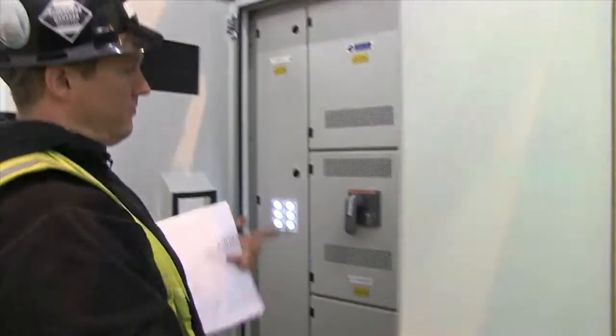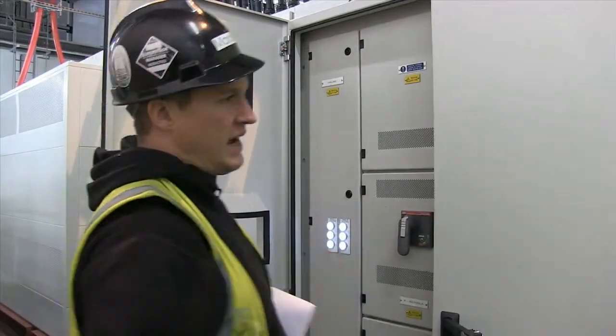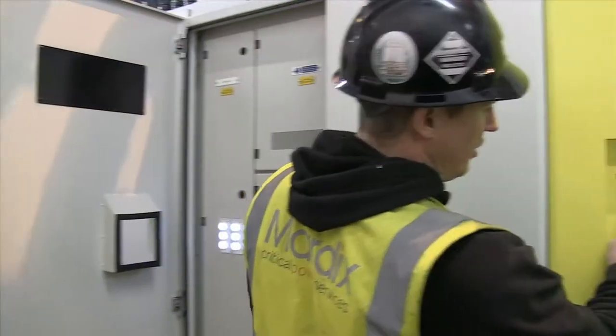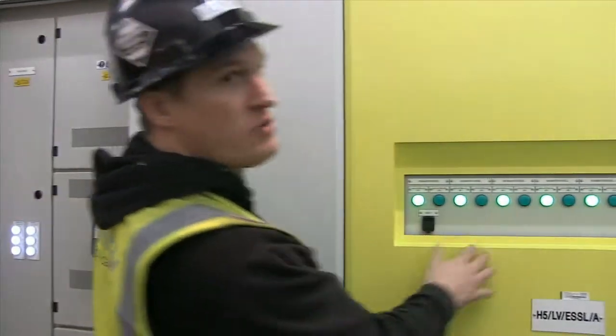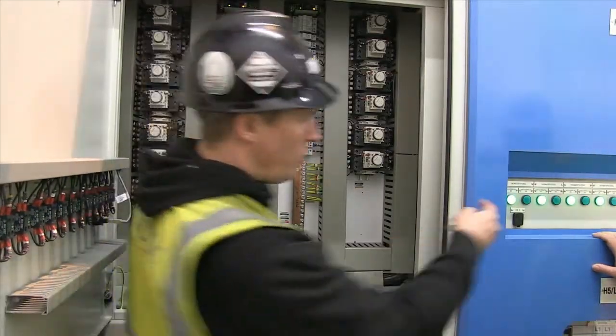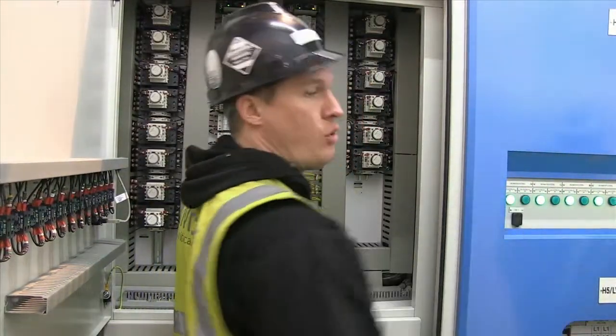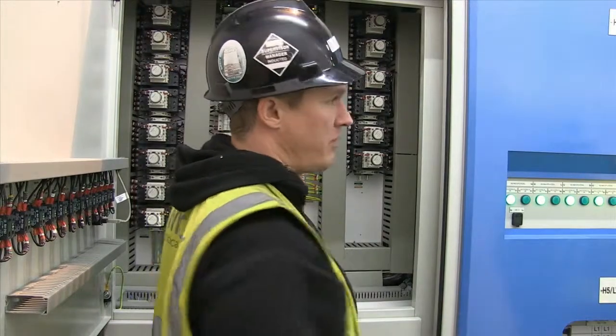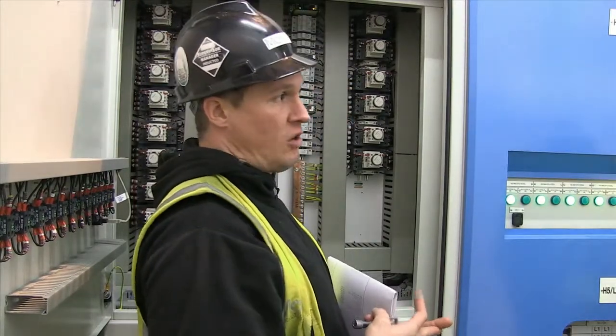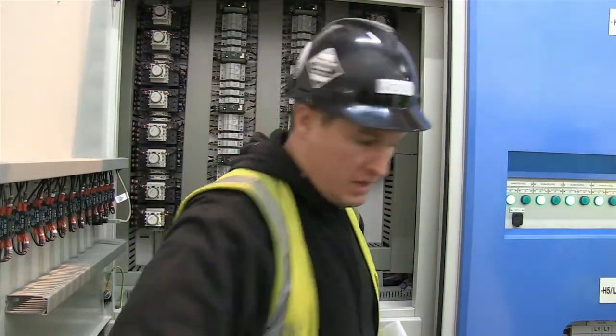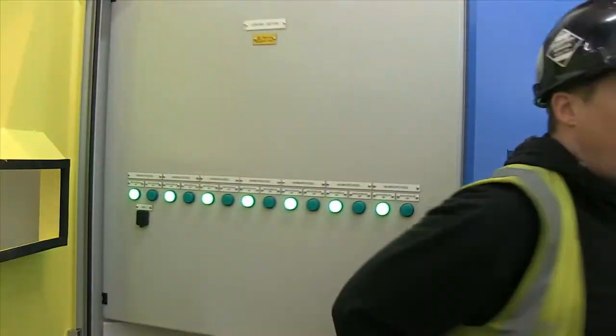So, example, if I killed that A supply there, A lights on, A lights on, you can see the whole panel's on A. All that would happen is, after 3 seconds, all of the lamps will go bang, bang, bang, bang, bang. They'll all go over to B, so it'll just flick over. But you'll have a 3 second loss, so there'll be a delay. The critical panel, you won't see any loss.